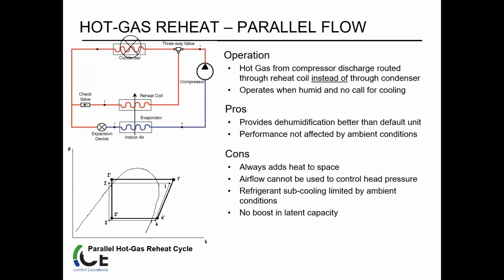So a parallel flow is very similar in operation. Compressor again, three-way valve controls the condenser bypass line. In dehum mode, the three-way valve sends the hot gas refrigerant to the reheat coil. Indoor air is reheated to neutral temperature, just like before, just a different path here. The outdoor condenser is completely removed from the flow path. The reheat coil serves as the only condensing coil. So that's a little change with parallel versus series. And then this supply air is basically the same process, heated to neutral temperature.